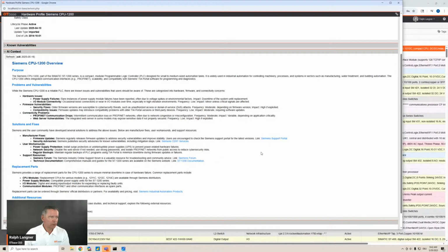And this is where, again, the AI context is very good at, to make you aware of, for example, connectivity problems with the Siemens S7-1200. It tells you there are some issues, Profinet communication drops.